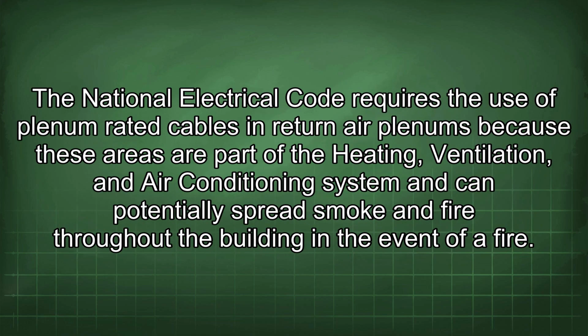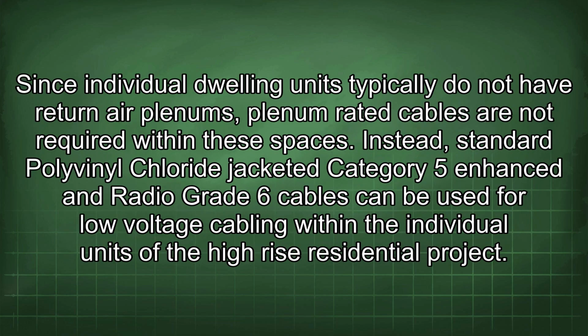The National Electrical Code requires the use of plenum-rated cables in return air plenums because these areas are part of the heating, ventilation, and air conditioning system and can potentially spread smoke and fire throughout the building in the event of a fire.